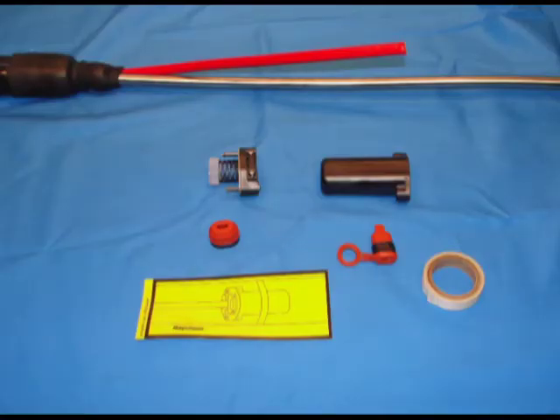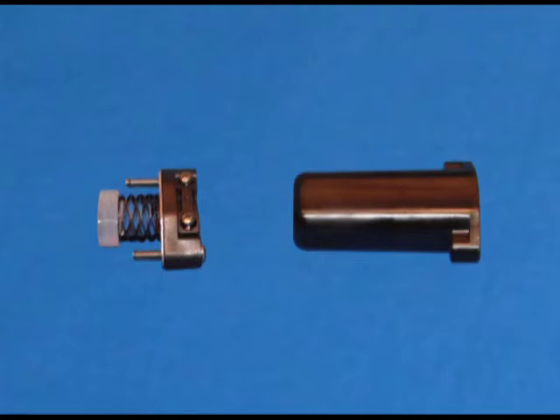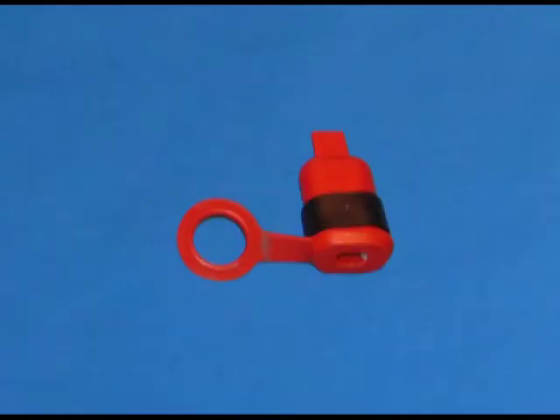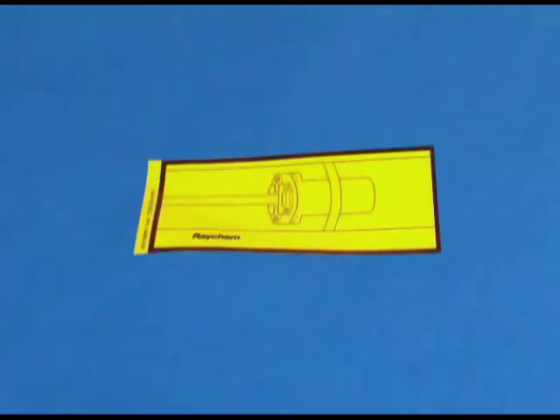Let's take a few minutes to review the terminating of the heat tracing at the other end of the tubing bundle. The E150 is a cold applied, low profile, end seal. It is designed for use with Raychem brand heating cables. It is approved by FM, the CSA, and the PTB for use in hazardous locations. The E150 kit contains one end seal enclosure housing, one sealing grommet assembly, one sealing boot, and one identification label.